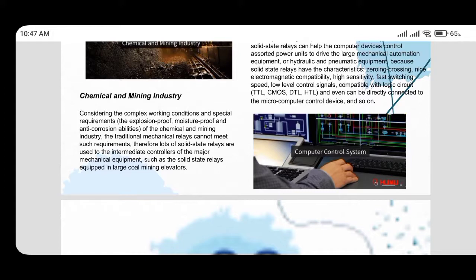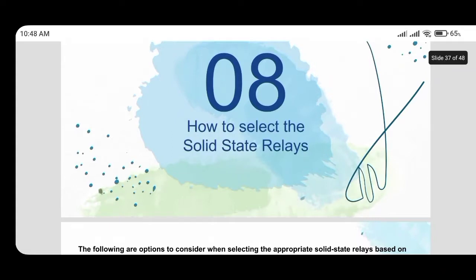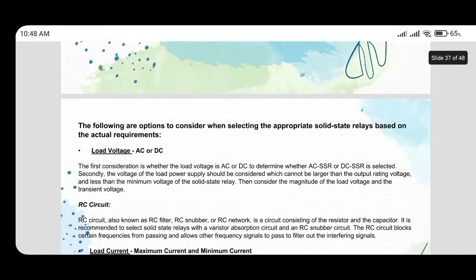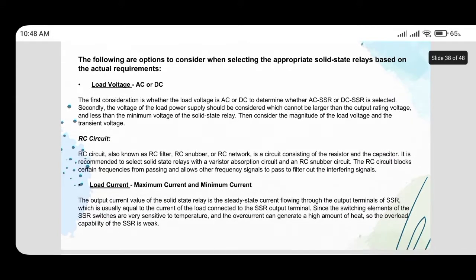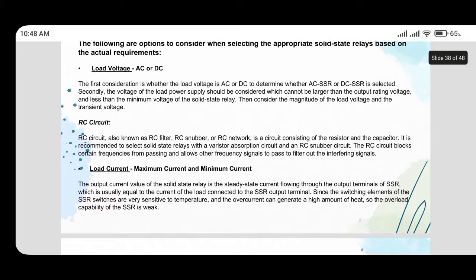How to select solid state relays? The following are options to consider when selecting the appropriate solid state relay based on actual requirements. The first is the load voltage, AC or DC. The first consideration is whether the load voltage is AC or DC, to determine whether an AC SSR or DC SSR is selected. Secondly, the voltage of the load power supply should be considered, which cannot be larger than the output rated voltage and less than the minimum voltage of the solid state relay.